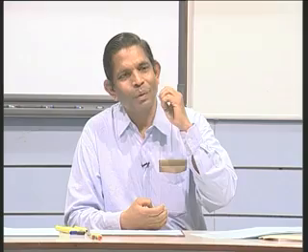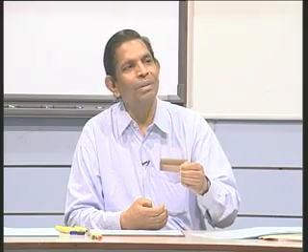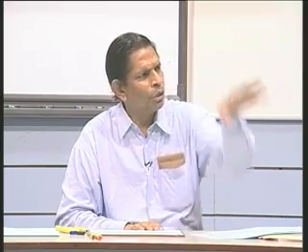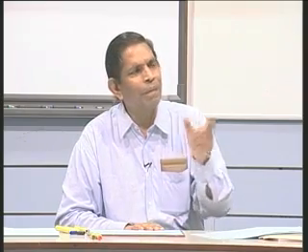Now, I want to point out one more point here. There is a last point, that the coherency behavior depends upon the location of the disturbance, because when I discussed the definition of coherency, we wrote a particular location for the fault or disturbance. Generally what is done is that, suppose in a particular system I am interested in knowing the dynamics, that becomes my location for the fault, and I find the equivalent for the whole thing.